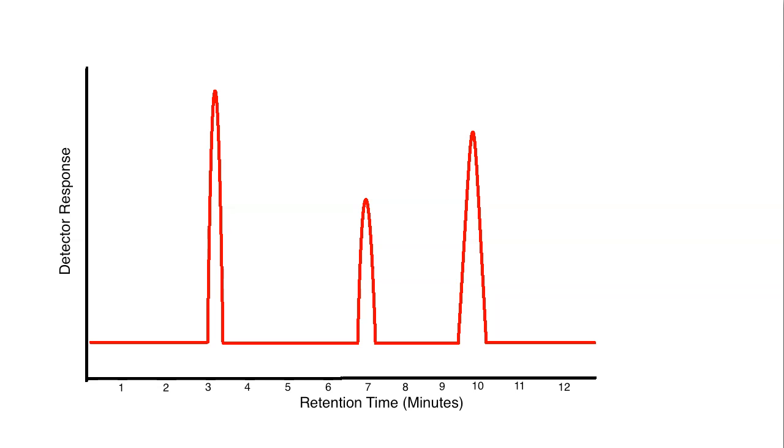Once it is in a gas phase, it's going to continue to be pushed by what's called a carrier gas. That's usually some sort of inert gas like helium or nitrogen that carries the other gases through a very long internal column. It's like a pipe that's twisted up for many, many feet inside of the gas chromatograph instrument. When it finally gets to the end of that column and it's pushed onto the detector, the detector has a response, and that response is what triggers the formation of these peaks that you see in the readout.